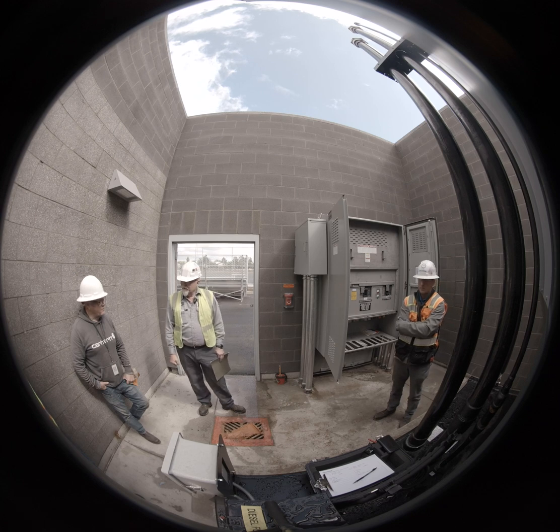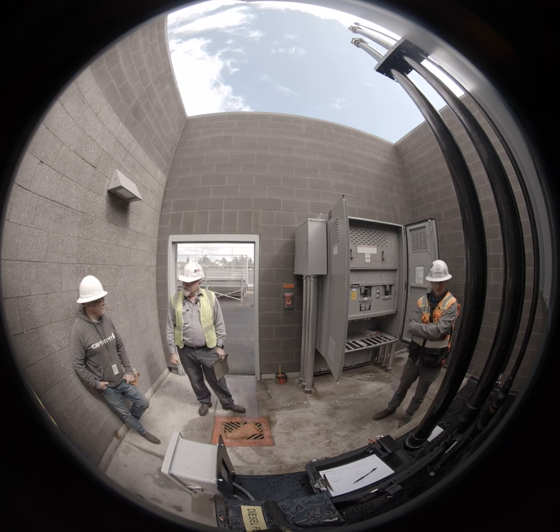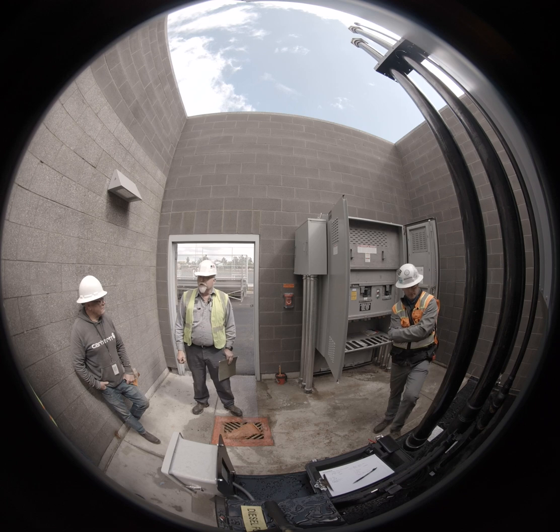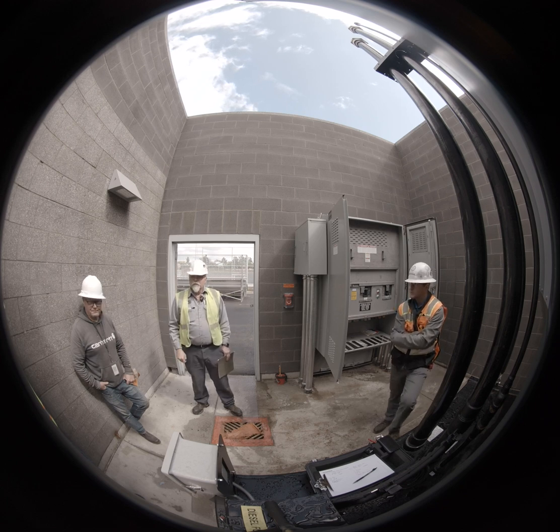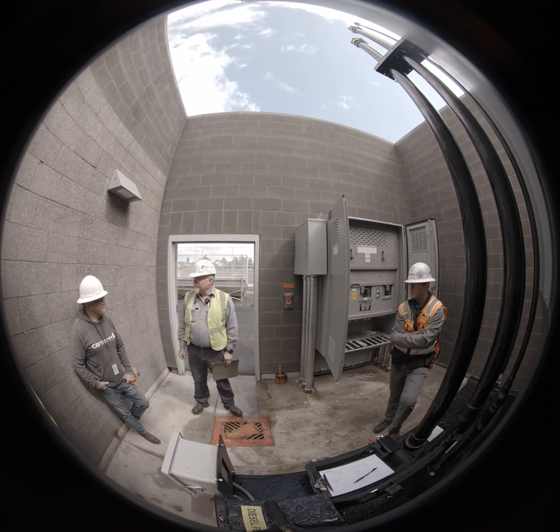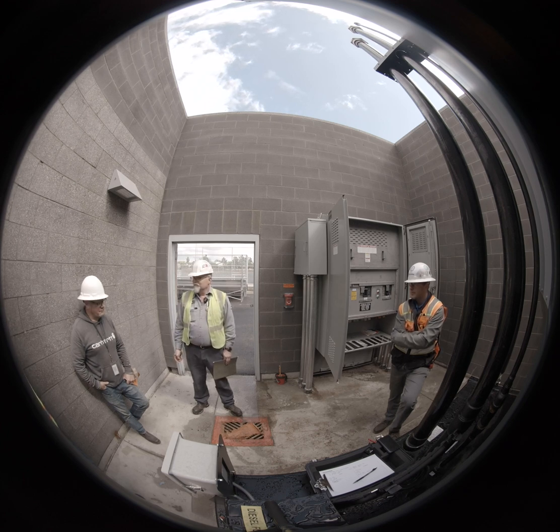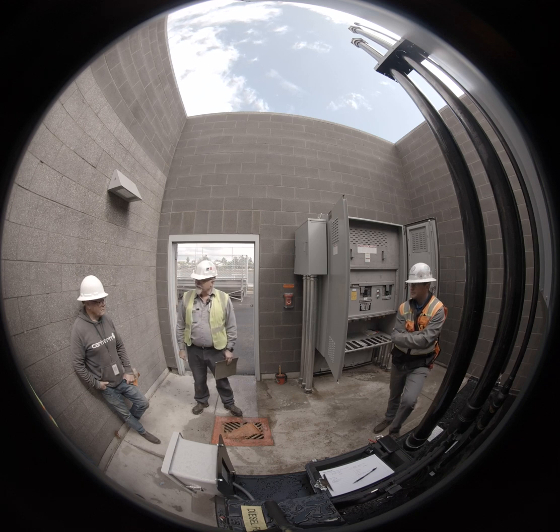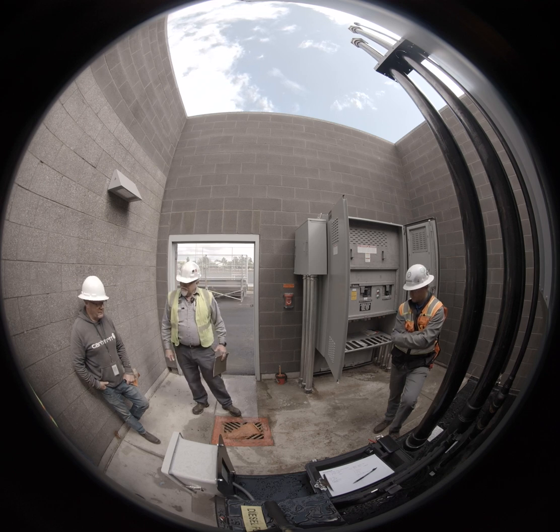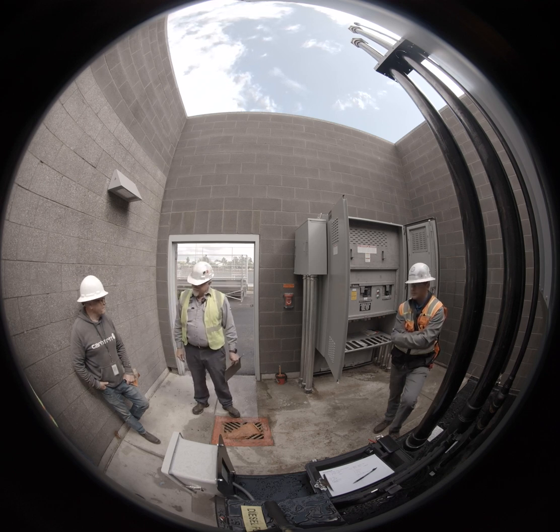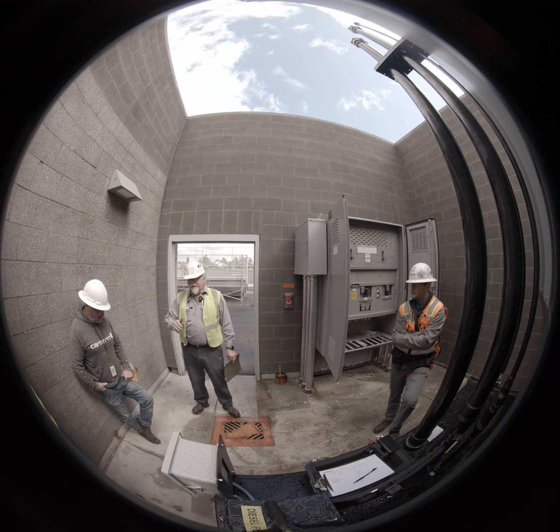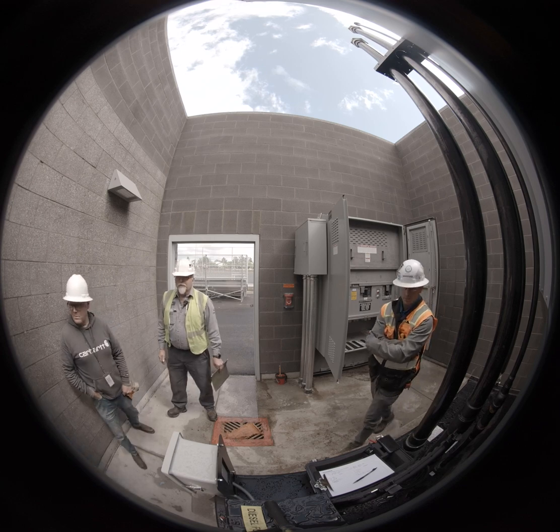Where would that information be? Exactly what the fuel burnage per hour is? The fuel burn will be in your O&Ms, which, when we get up here, there is a CD of the O&Ms for this machine, and also the cut sheets. The original cut sheets will give you the 25, 50, 75, and 100% burn rates. Okay. EPA, I have to give that to them. Yep. Okay, well, let's move on down the road here, and we'll go a full circle on this guy.